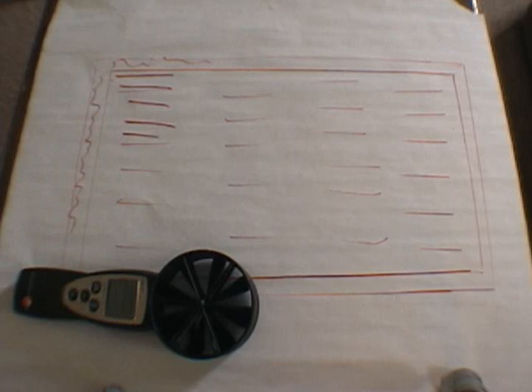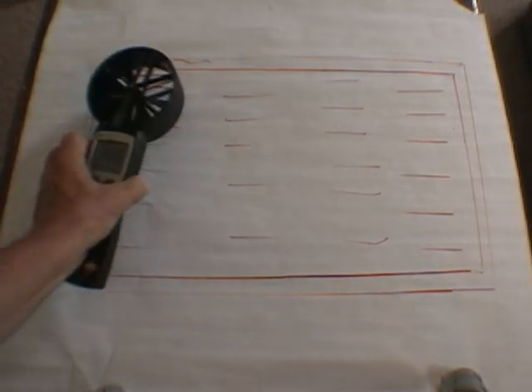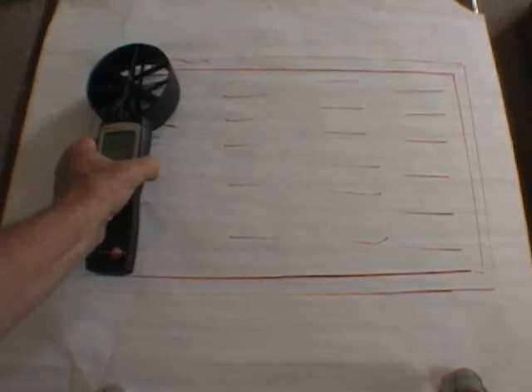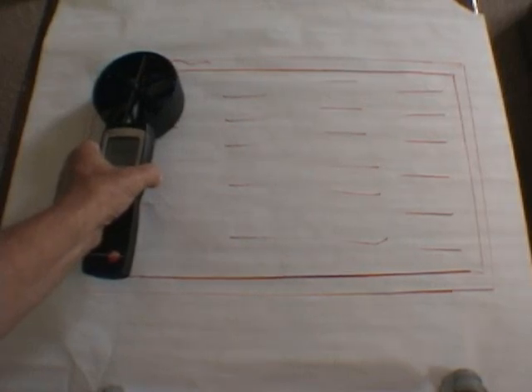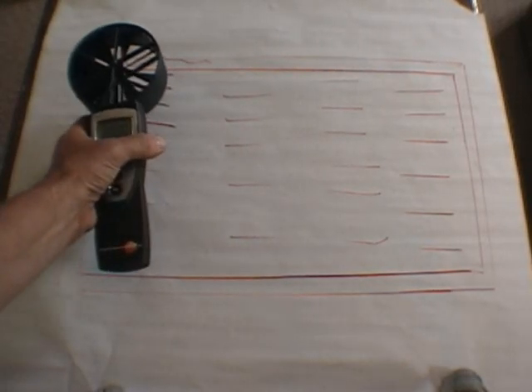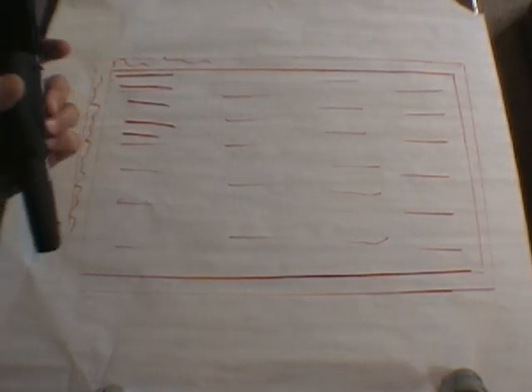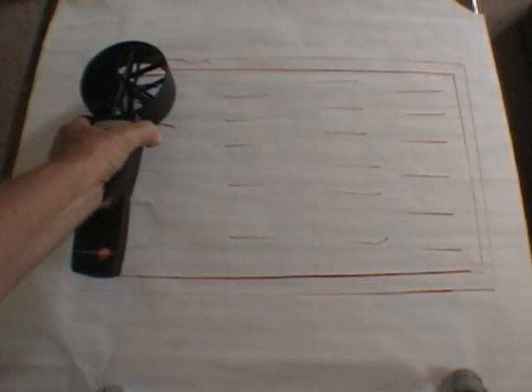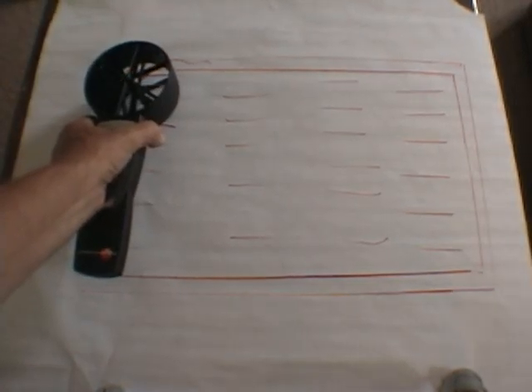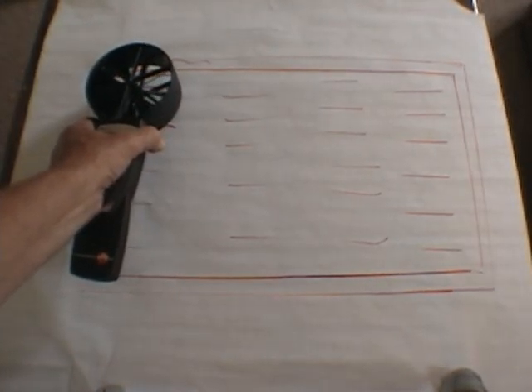We want to measure the face of the open area and take our reading over the open area. So I would place the vane inside the open area, one inch off the top of the face of the grill. I'm going to use my finger. My finger's first joint is about an inch, and I'm going to use that as an offset to keep it one inch off the face of that grill.